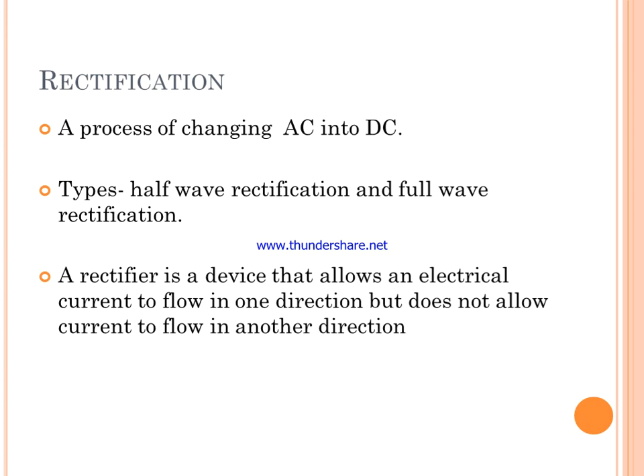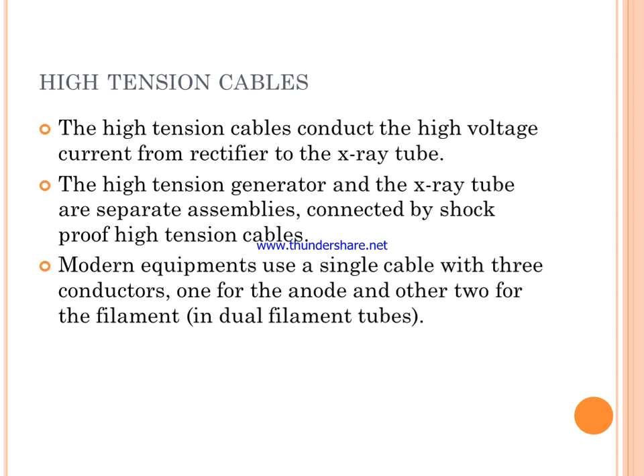Types of rectification are half-wave rectification and full-wave rectification. A rectifier is a device which allows electrical current to flow in one direction only. The high tension cable conducts high voltage current from the rectifier to the X-ray tube. X-ray tubes are separate assemblies connected by shock-proof high tension cable.